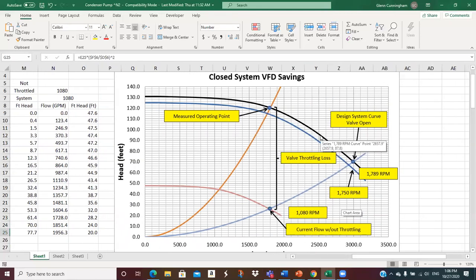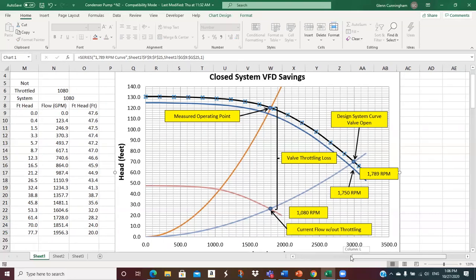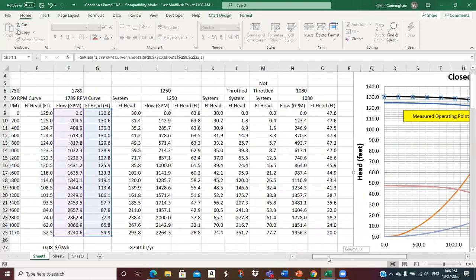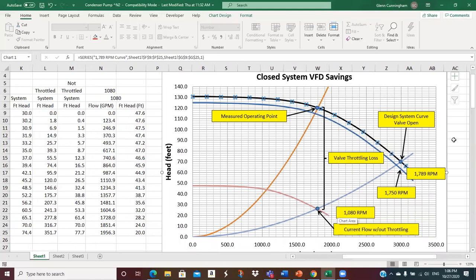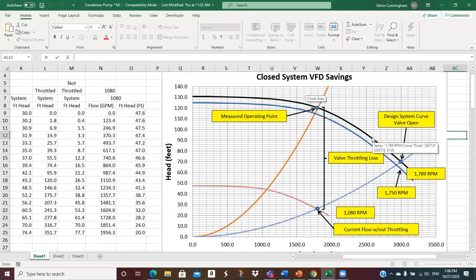So if I click on this one, it should show that that's being plotted. There it is, right there. Okay, so for my analysis, if that's what I measure, this is my adjusted pump curve based on my true operating speed. So that's the capabilities of that pump at that speed according to the manufacturer. Now, that's if the impeller's good, and that's if this representative curve was representative of my pump when it was operating at 1750. There's lots of possible variation of it.